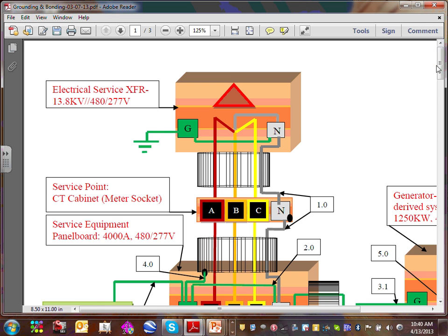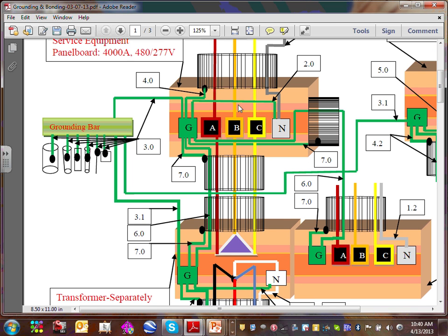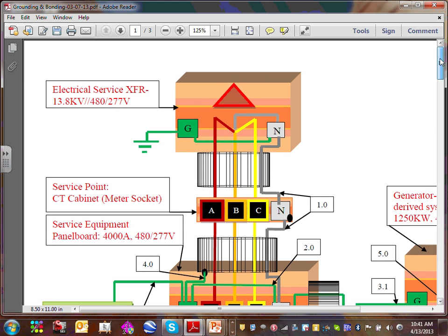Change this one, guys, like I said, instead of 4,000, make it a 400 amp panel, and make everything else like a 100, 60, or 200 amp panel. The same calculation applies. Smaller system, no paralleling, but I picked the big sizes because they get you into the paralleling, which complicates things a little bit. Any comments, any questions, guys?